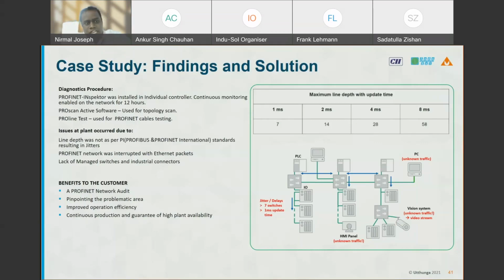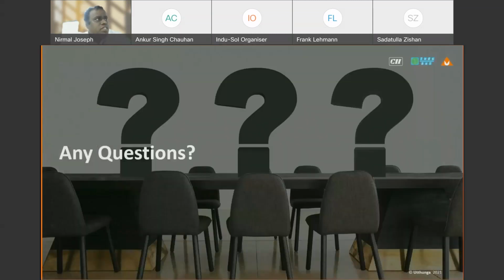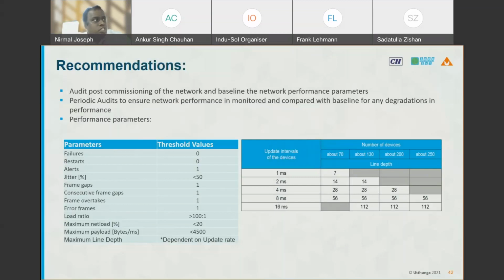As a final slide with some recommendations - Frank, can you move to the next slide please? Generally, having an audit post-commissioning of the network is beneficial, and this becomes the baseline for the network and performance parameters in your plant. Based on this reference, you can have periodic audits to ensure these parameters are monitored and compared against the baseline. If you find any degradation in performance, this can call for early maintenance, reducing your plant downtime.